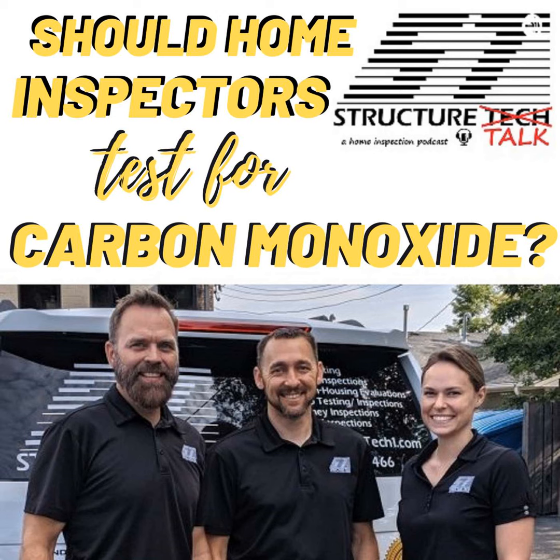Why is that? Just because it's a bigger flue, bigger diameter? It's because there is no fan that's going to swirl all those gases around and mix them up. They're just rising up through gravity. That makes sense. And I mean, boilers are going to have different burners, and you could have one burner that's really bad, and one side of that flue might have really high levels of CO.